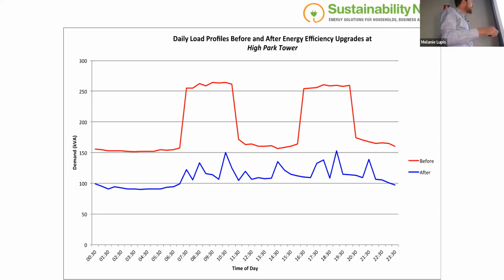So the carbon monoxide sensors fix that, but then we also dropped their base load by 50 kVA as well, and that was the condenser water pumps. Basically running those a lot lower, and then they've just got a few little spikes, which could be the car park fans just kicking in as needed. It's actually safer too, because if an old car started up in the lower part of the basement and ran idle for a while, that could have been creating very unsafe air quality down there.